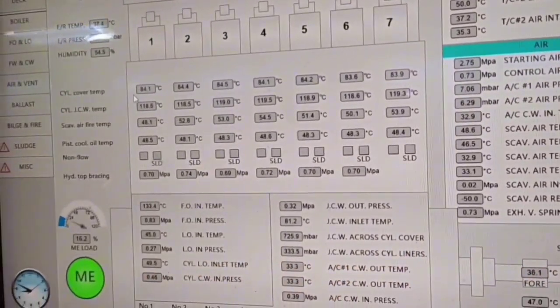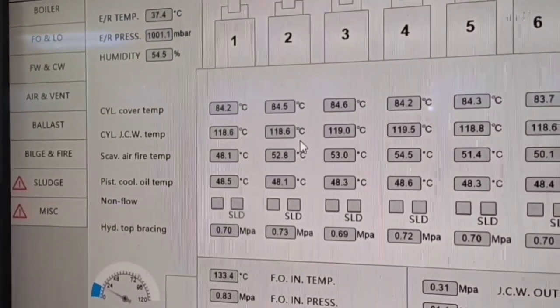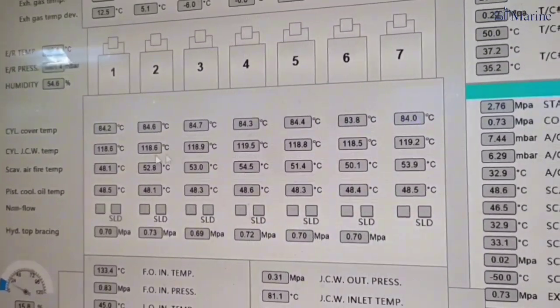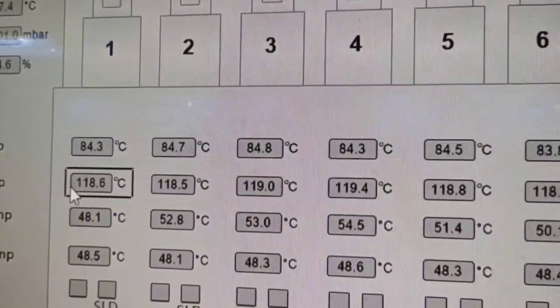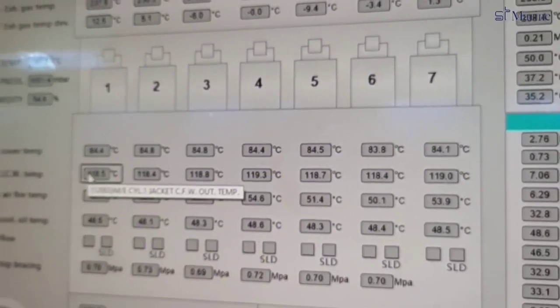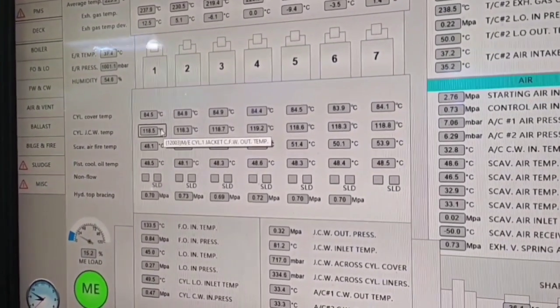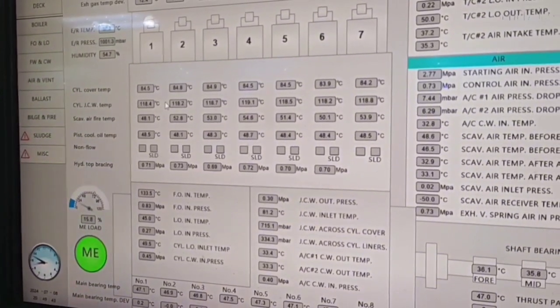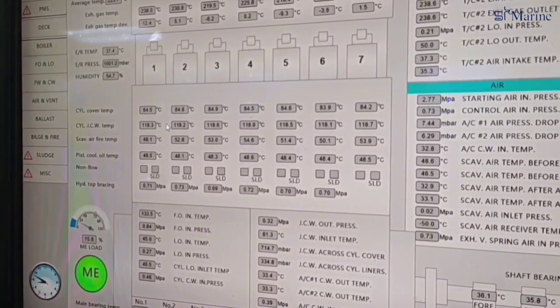So here we have to wait for the temperature to fall down. The temperature is around 118 to 119 degrees. Since we have changed the sulfur content from high sulfur to low sulfur, these values will start dropping to around 80 to 85 degrees, same as the cylinder cover temperature. This will take around 10 to 15 minutes.